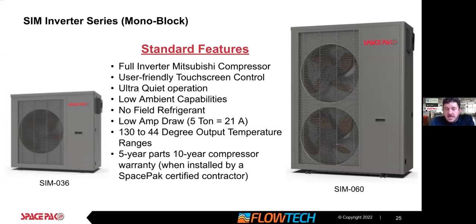When you're electrifying a house, an existing house or a new construction house, and sizing your panel, it's nice to know that your heating, cooling, and domestic will be requiring maybe a 30 amp breaker, maybe a 35 amp breaker, and the running amps is 21 amps. That's a big advantage of these units versus other electrification equipment.